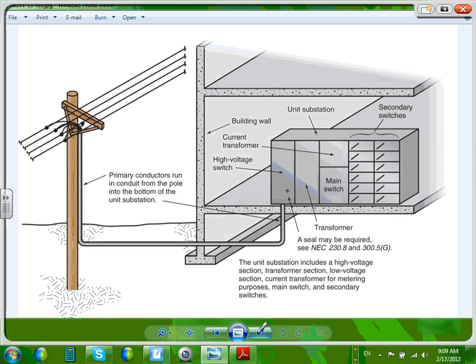This one, if you look at it, primary conductors in conduits from the pole into the bottom of the unit substation. I have a unit substation coming in, mostly in industrial, and this one is for 4160 volt, 460 volt, right? And just put voltages here, 4160 volt or 13.8K. You brought the power in here into your unit substation. Can you see the high voltage switch gear with a fuse, current transformer, you meter it. You also have the transformer section right here, the high voltage section right here. Then from that transformer, you went into the low voltage section and into your 4000 amp switch gear.